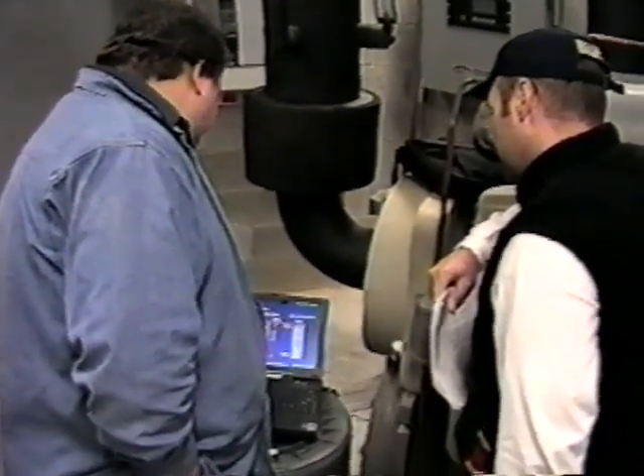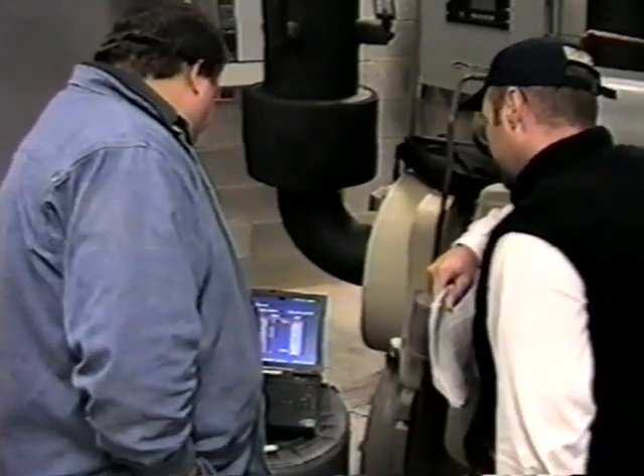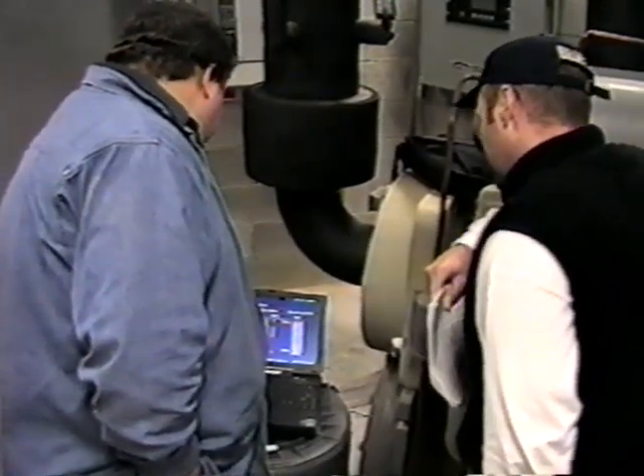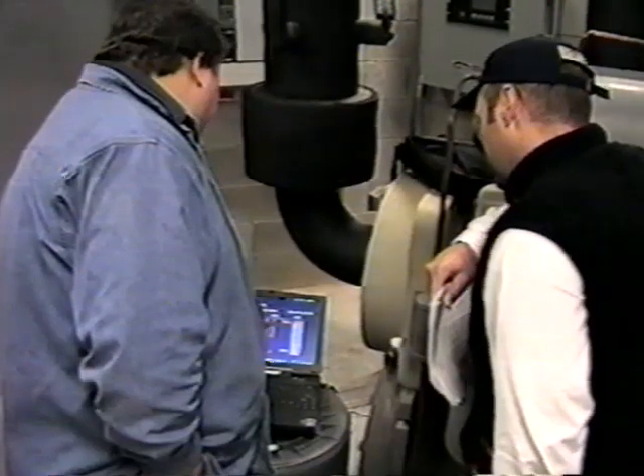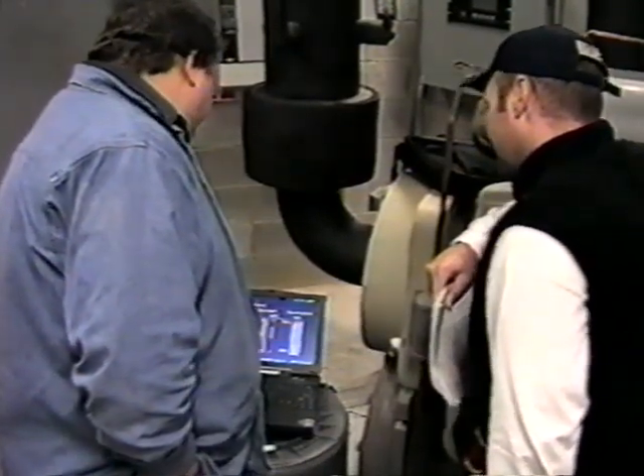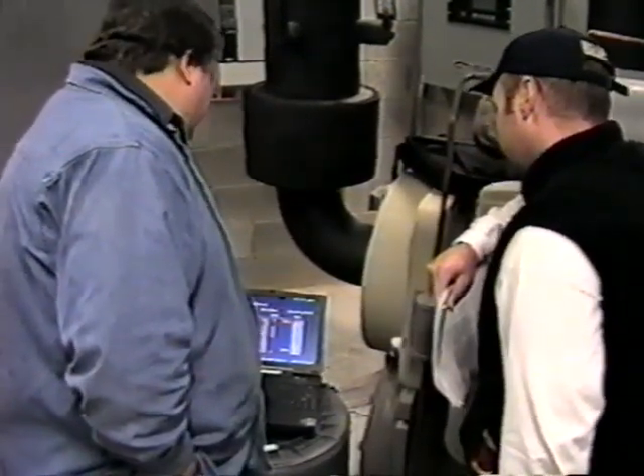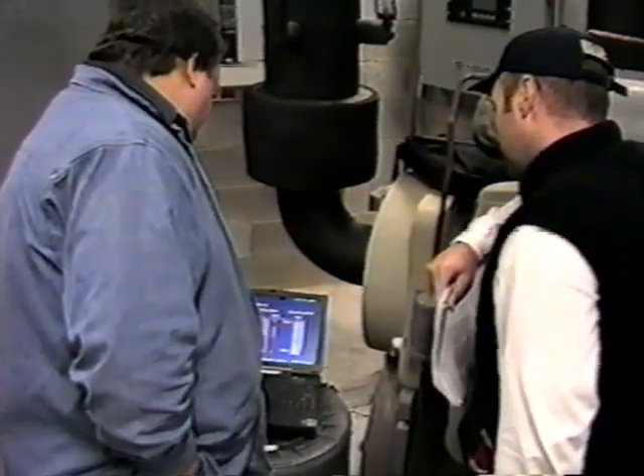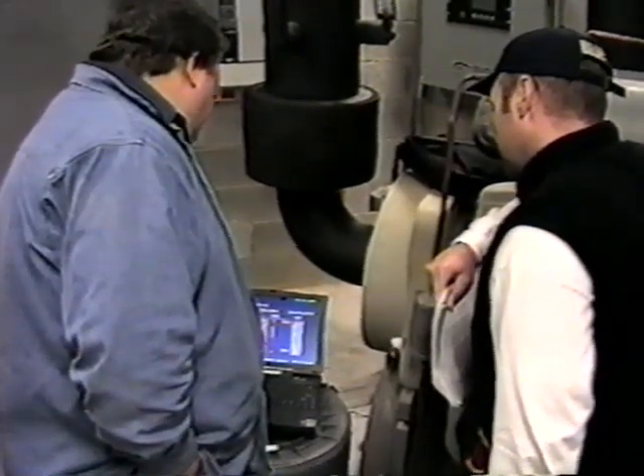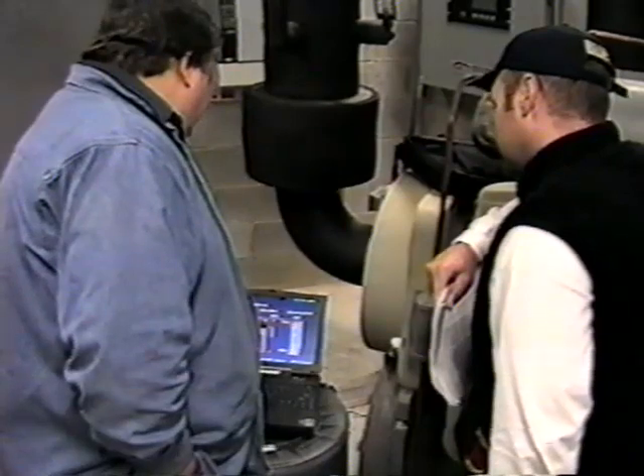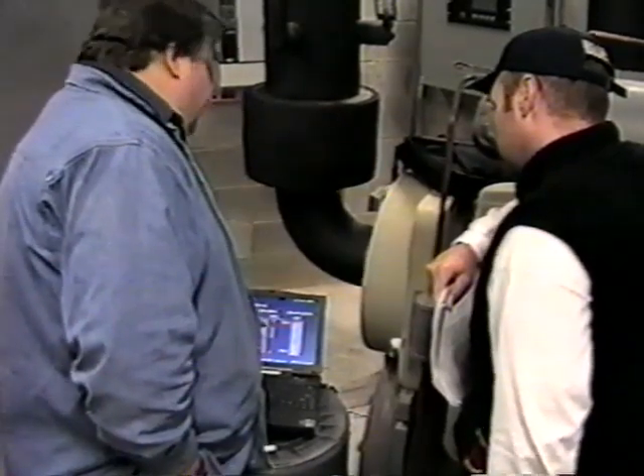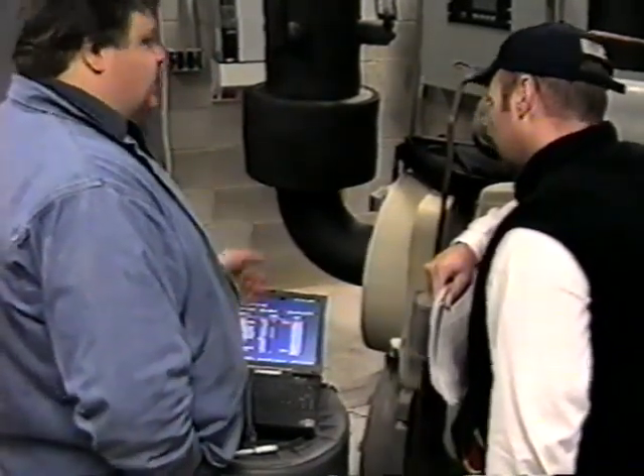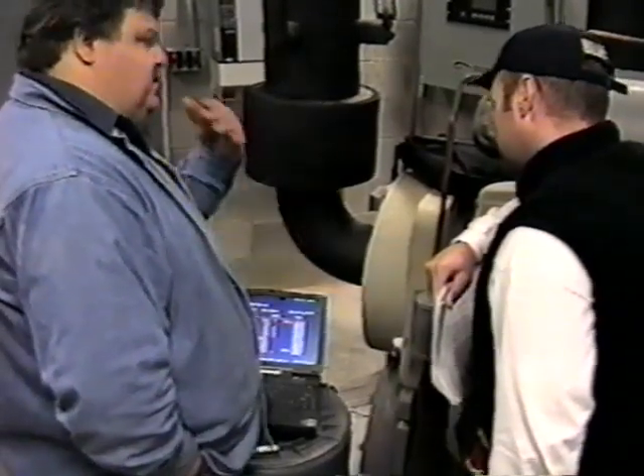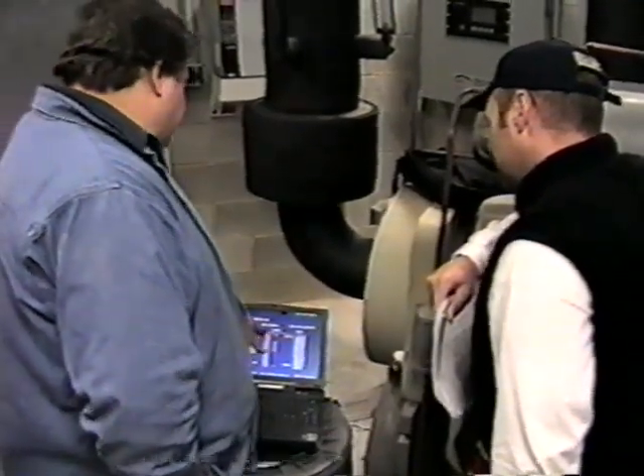But what this is, well, actually, it's calling for high speed, and this is a confirm. It's on low speed, right. It's calling for high speed. This is the status. So this tells me that I wanted high speed here, did I get it or not? If this goes to high, then the chiller is enabled, so then the chiller can go through its startup sequence and all that. So you're going to see things in here.